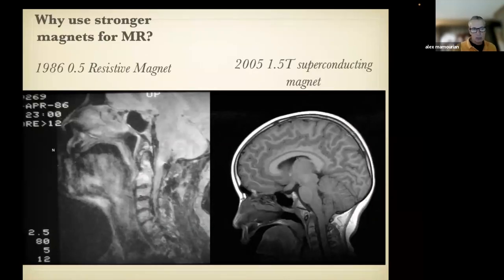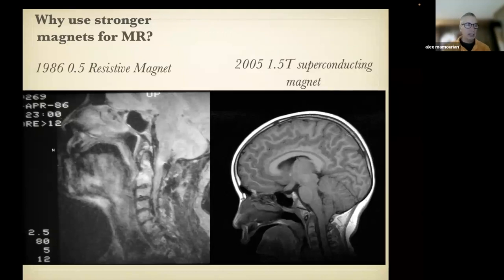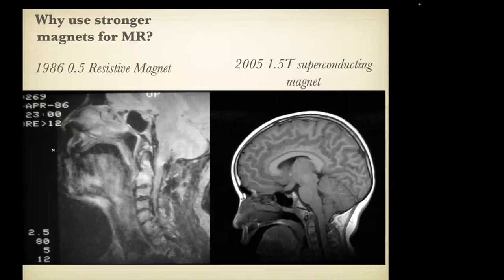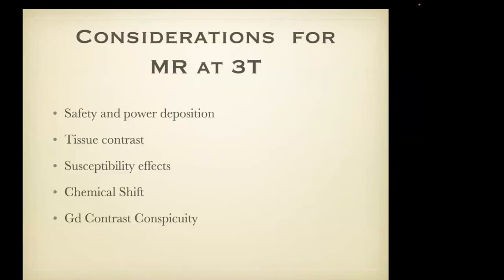This is two different patients, but the image on your left is a patient scanned in 1986 on a 0.5 Tesla resistive magnet — I don't think anyone is still using resistive magnets, but that's what we had at the early clinical use of MR. The image from 2005 is from a 1.5 Tesla superconducting magnet. More is better in this case, and there were a lot of benefits in going to 1.5 Tesla, but the logical extension to 3 Tesla was not as transparent.